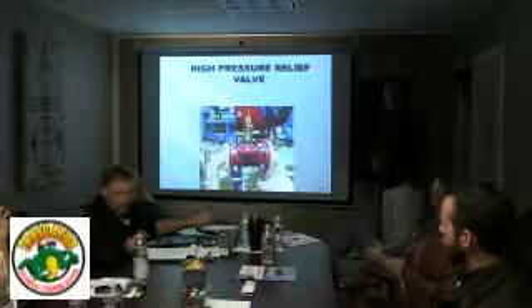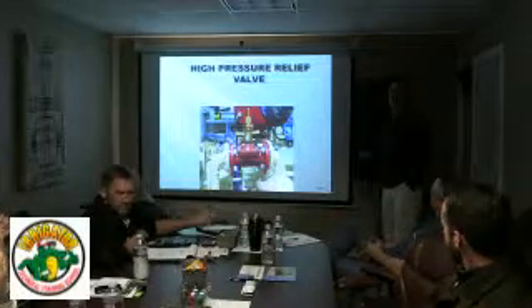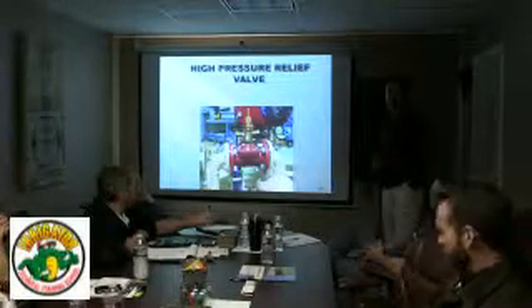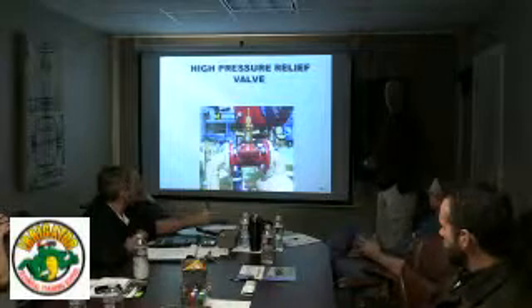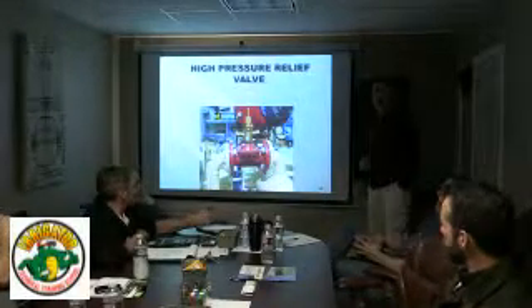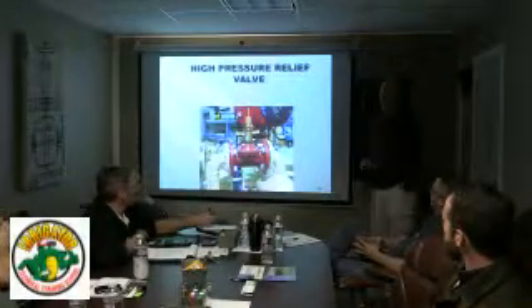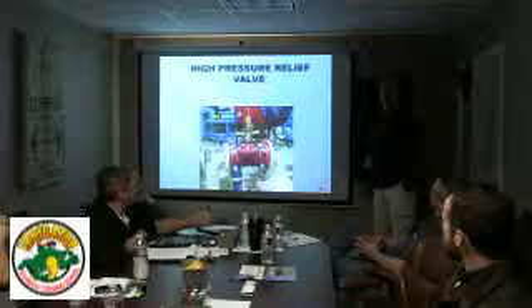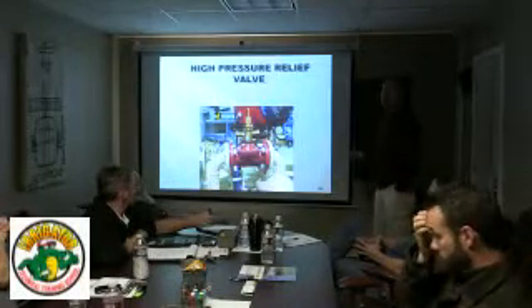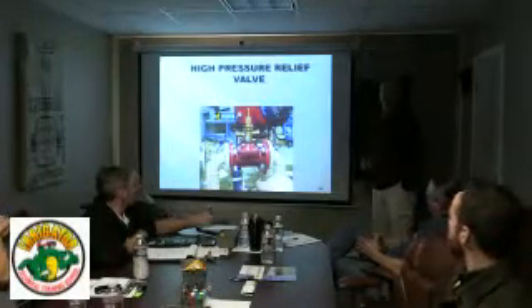Would that be like a PRV as well? It is a PRV. A lot of people call it a PRV. It has a life on the spring and everything in there. It should have normal maintenance. Replace it every 10 years, 5 years? Yeah, if that. Depends on the water quality. I've torn a lot of these apart, cleaned the sediment out, and got them going again.